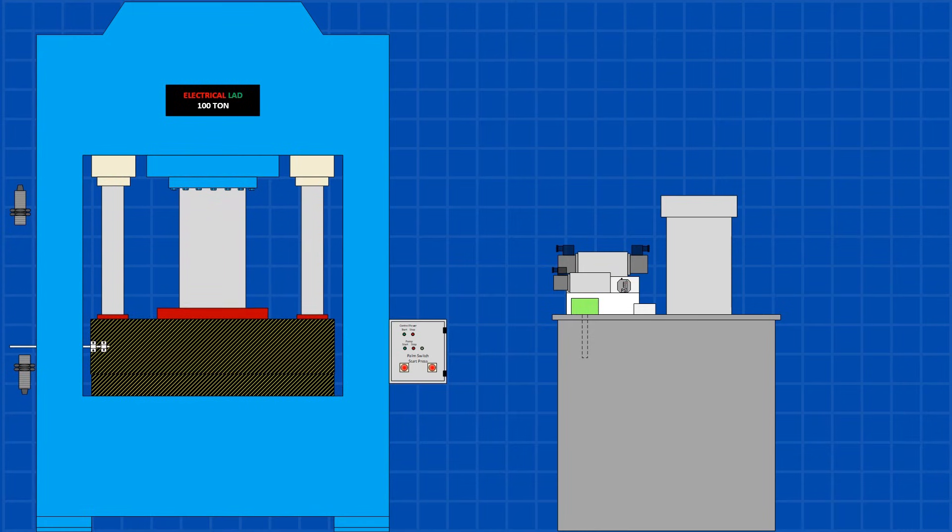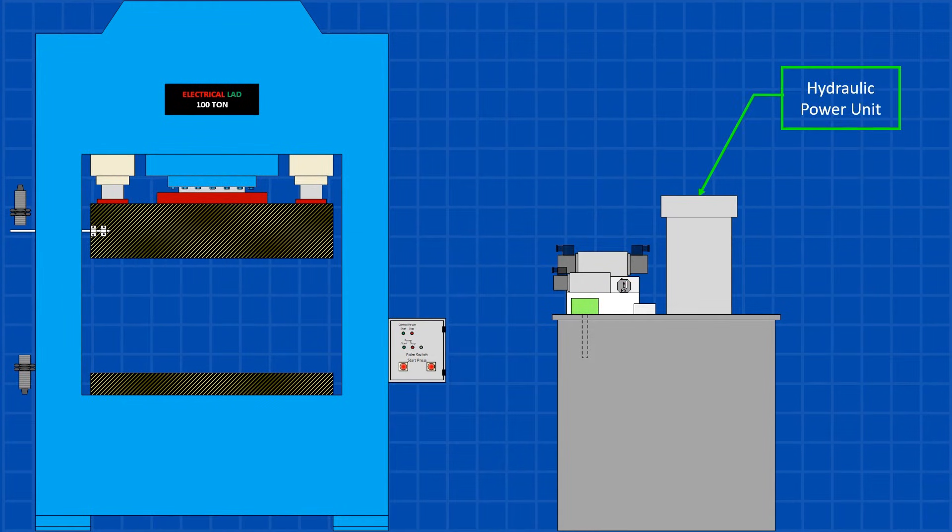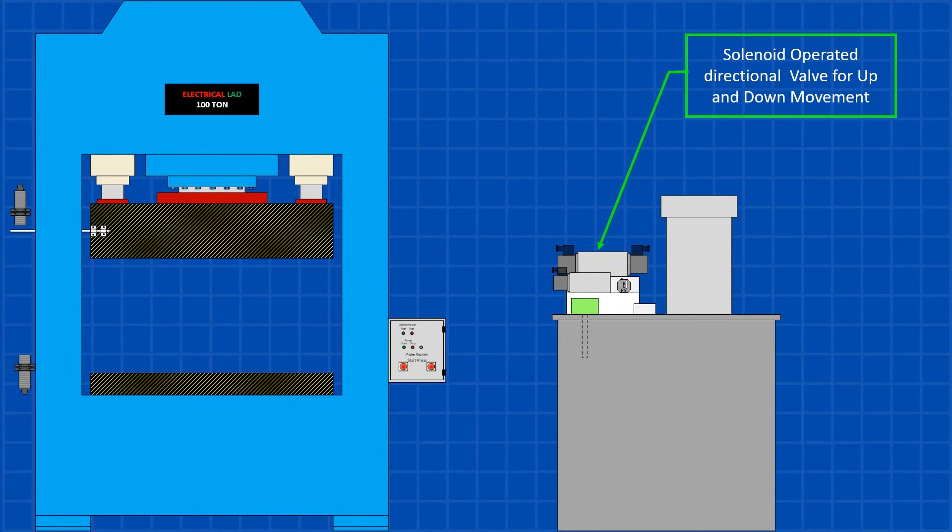The hydraulic press relies on a power unit that delivers fluid to the cylinder at a specified pressure. In addition to the pump and motor, a four-way three-position directional valve, when energized, directs fluid to the cylinder, enabling its up and down movement.